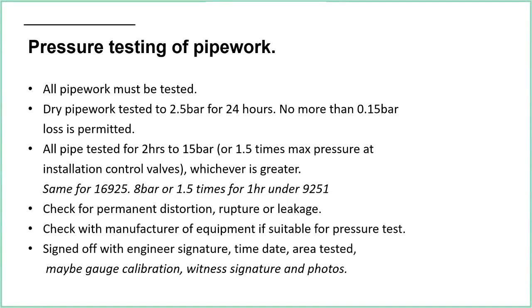Pressure gauge calibration is important. I've said maybe on the screen there; maybe I should update that to probably. Gauge calibration, so you need to see some sort of certification. There's no real point doing a pressure test on a gauge which is unreliable, because it might be giving you the wrong reading. Maybe it's too low, so you've not really carried out the test, or maybe it's giving you a reading which is too high, so you're actually testing to a higher pressure than required, which obviously may cause other issues.